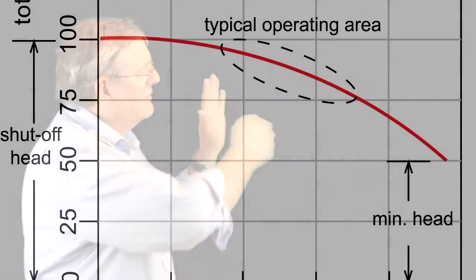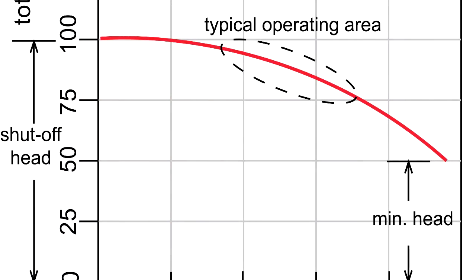Pump manufacturers will provide information on their pumps in terms of a curve. This curve shows head on the vertical axis and flow on the horizontal axis. The characteristic is that the head starts high and drops as the flow increases, to a point where we have minimum head.